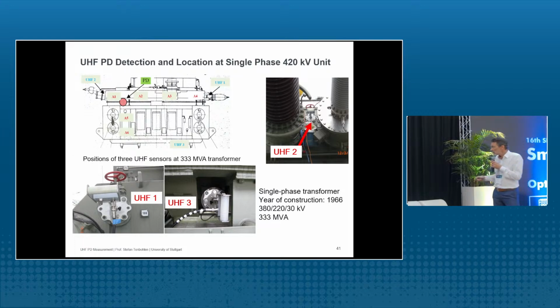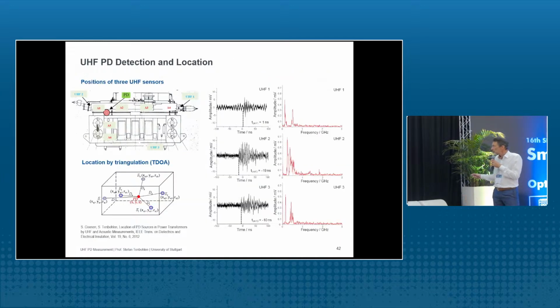So we installed UHF sensors. We have here 3 UHF sensors, here one at the bottom and here and there, because there were oil valves, and measured with these UHF sensors the signals. You can see here the responses on different positions. Here UHF sensor 1 is here, 2 is here, 3 is there. And you can see there are time differences between the signals. Time differences because the electromagnetic wave has to travel from the origin of the PD to the different sensors.